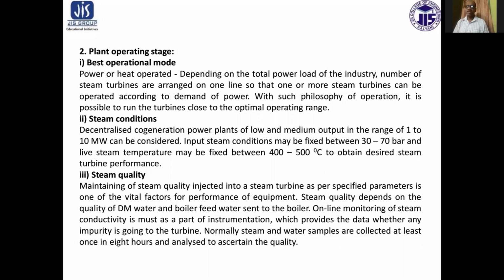Online monitoring of steam conductivity is a must as a part of instrumentation, which provides the data whether any impurity is going to the turbine. Normally, steam and water samples are collected at least once in 8 hours and analyzed to ascertain the quality.